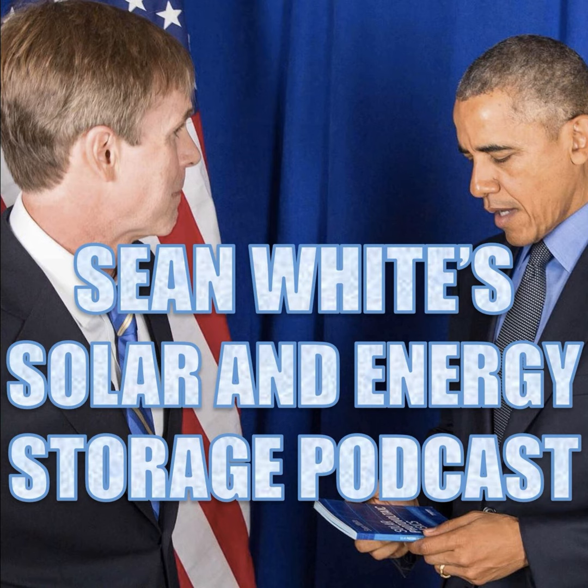Maybe you have PV connected to that DC bus and then off to an inverter. So if you turn off the energy storage system with that disconnect, there might still be some voltage at the battery and then some voltage on the other side of the DC bus, maybe coming from the PV system or back from the grid. Then you would need to have a sign right there.